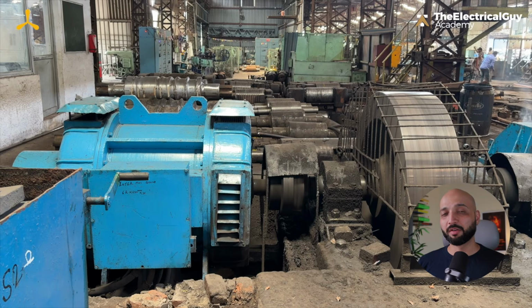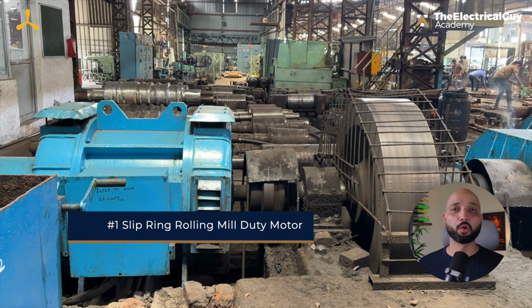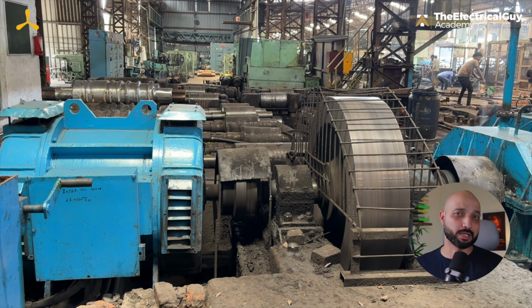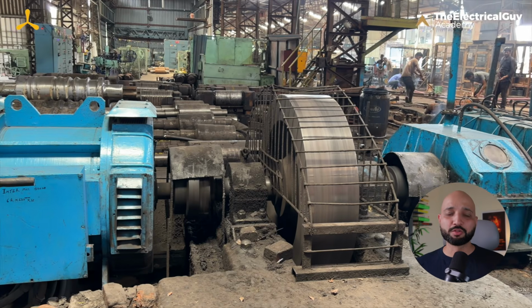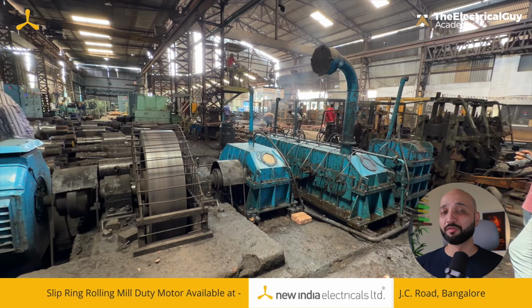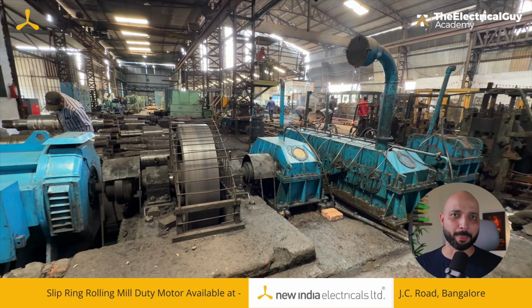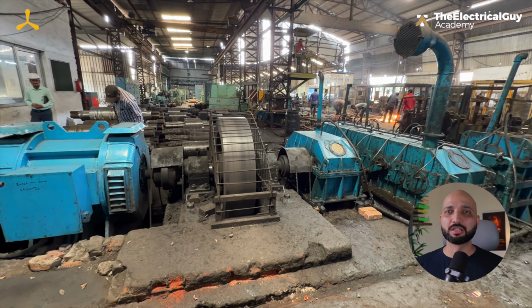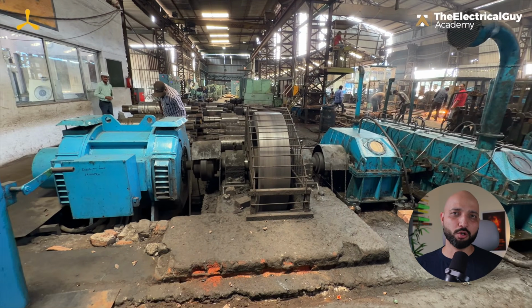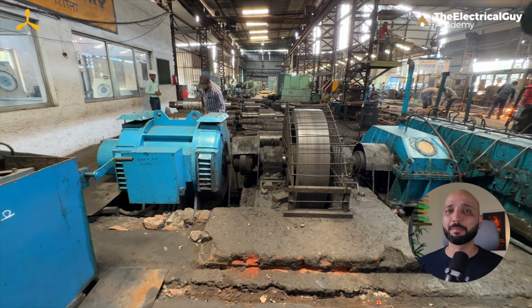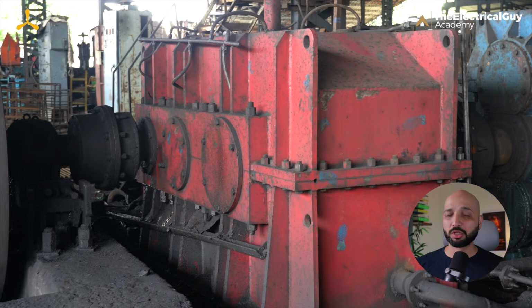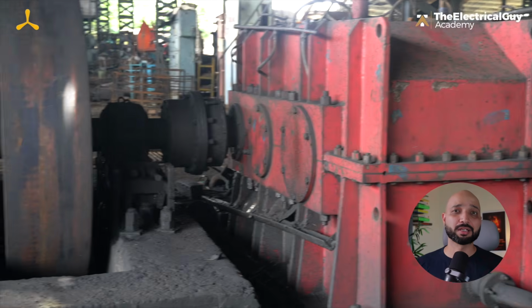The first motor that we are going to see is a slip ring rolling mill duty motor, also known as a roughing motor. These motors are specifically designed for a very heavy duty application. In a rolling mill, the motor does not get a smooth and comfortable load. It has to handle severe mechanical shocks, sudden load changes, high transient torques, and extreme thermal stress. In simple words, this motor is built for abuse.